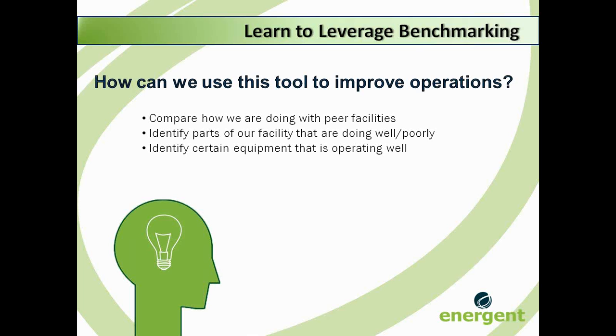We can look at our heating and cooling information to identify equipment that is working well. For example, if our weather-related benchmarking tool is in the 75th percentile during the winter, but only the 25th percentile during the summer, we know that our cooling system must be looked at, but our heating system seems to be working well. Without this granularity, a hospital may think that they are performing well in the 50th percentile without the different commodities being measured. Finally, hospitals will understand that they operate at different levels of efficiency depending on the season. This is all available from the Energent benchmarking tool.